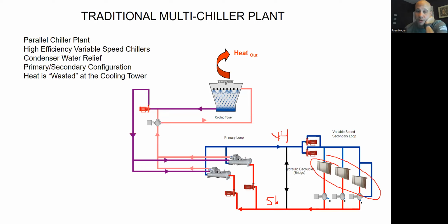Once it removes the heat from the water to send cooler water back, now it's got this heat from the water that it has to do something with. It uses the refrigeration cycle to change its pressure like we did in module 1 to boost up the pressure higher, which boosts up the temperature, which allows me to reject the heat to a warmer water loop. So this condenser water loop historically is providing me 85-degree water, and I am sending it 95-degree water back. It doesn't have to be these numbers. These are just the standard numbers you typically would see on a historical design.